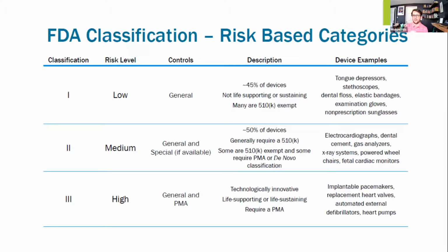And then some of them require what's called a de novo. These types of devices are medium risk, and they are things like ECGs, dental cements, dental implants, knee implants, X-ray systems, fetal cardiac monitors, and thousands of more examples. And then the last one is class 3 products, which are the highest risk products. Those are going to be the most technologically innovative, the life supporting, life sustaining, and they require what's called a PMA, which is a pre-market approval. These are typically implantable cardiovascular and neurology type things that could be life threatening if not done correctly. So you've got pacemakers, stents, defibrillators, pumps, deep brain stimulation devices, these kinds of things.